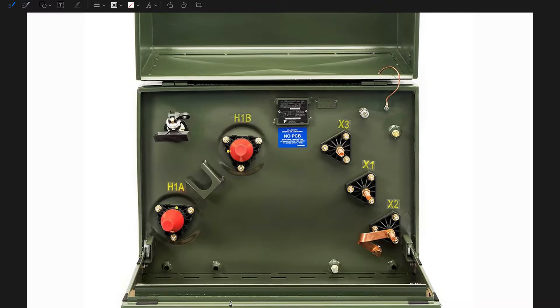The cable is going to come in - doesn't really matter which side because these work both ways. I'm just gonna draw it right here since we have more room. Your cable is gonna come in like this, you're gonna have an elbow. I have another picture to show you what an elbow is - basically the cable comes in like this, and this is your primary cable coming from the pole. This is gonna plug in here, and that primary cable feeds this transformer.